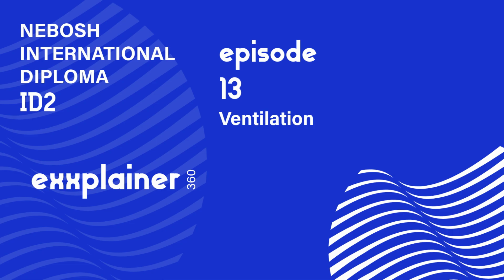And even with the right placement, you mentioned dead areas. Sounds ominous. It can be. These are just pockets in the room where the air isn't moving. It's stagnant. The air changes aren't happening there. How do you even know they exist? You can use smoke tracer tubes. Release a little smoke, and you can visually see where the air isn't flowing. But the problem is, they move. That's the kicker. They're unpredictable. Maybe you change where the makeup air comes in because it's winter, or someone props open a door. Suddenly, that dead spot full of contaminant shifts somewhere else.